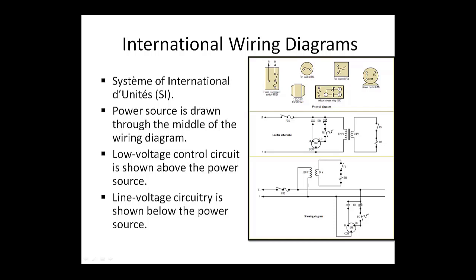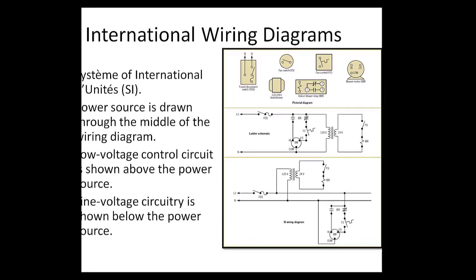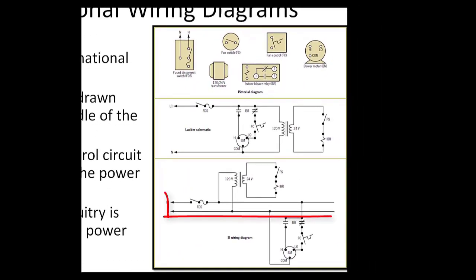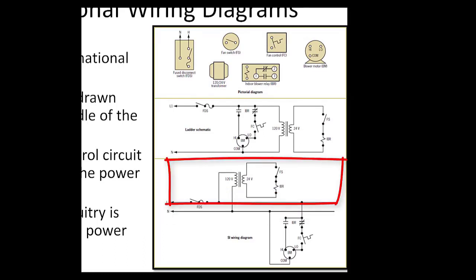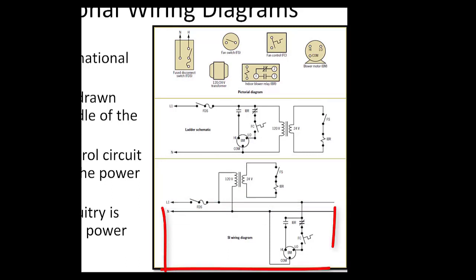Leaders in science and technology worldwide have used the Système International style of wiring diagrams, sometimes called SI. Within that system, the power source is drawn through the middle of the wiring circuit. The low voltage control circuit is shown above the power source, and the line voltage circuitry is shown below the power source.